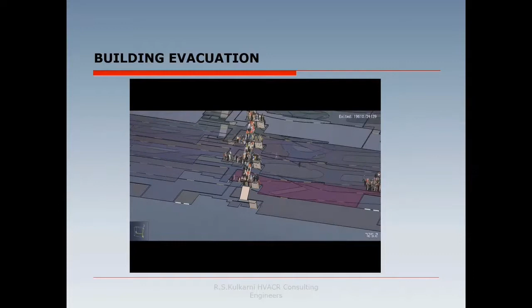Okay. Sir, if in a particular building our staircases have open window openings, is it mandatory to have a pressurization system? No, it is not mandatory. It was not mandatory till the 2016 NBC, because it is allowed if you have a 0.4 square meter opening in your staircase wall, then you could have natural ventilation for the staircase. But now that clause is changed in 2016, saying you should have openings but in the opposite wall, and rarely are opposite wall openings available in the staircase.